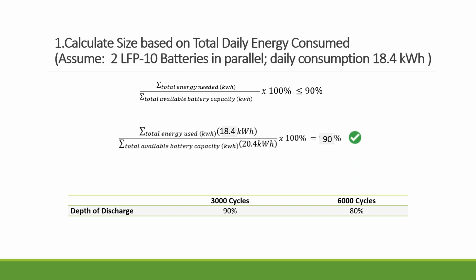Now, this project is mainly for backup, so 3,000 cycles is plenty for the customer. That's why we set it up with two of the LFP-10, which is about 20.4 kilowatt hour total energy, and the house daily consumption is 18.4. So we set it up at a 90% depth of discharge, so that works fine.